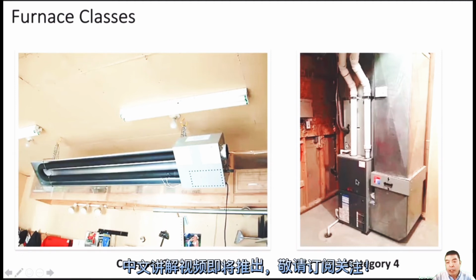And you know the high efficiency furnace has 2 heat exchangers. The secondary heat exchanger is just like the coil in an air conditioner, but inside is condensate water and flue gas. If the condensate water cannot drain out, the temperature is too low, so that will cause the coil to freeze. Sometimes it bursts the copper pipe. The secondary heat exchanger we normally cannot see. If you take the blower motor housing out, you can look at it from the bottom, but from the top it's hard to see.